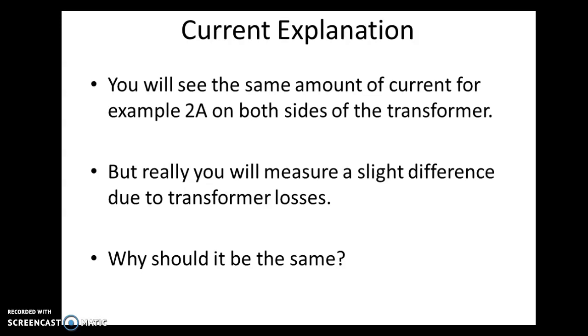For the current, as we've already mentioned once before, it should be the same from the primary to the secondary because everything is exactly the same as far as connections go. You will see a slightly lower current reading on the primary side for this one, in most cases due to transformer losses. But they should both be equal to the same volt amps at all times. So in some cases what you'll notice is if the voltage drops a little bit, you may see more current flow or vice versa, so that the volt amp calculation comes out the same.